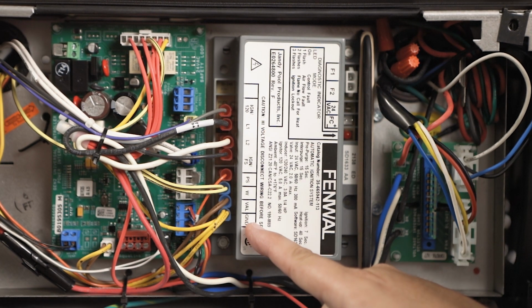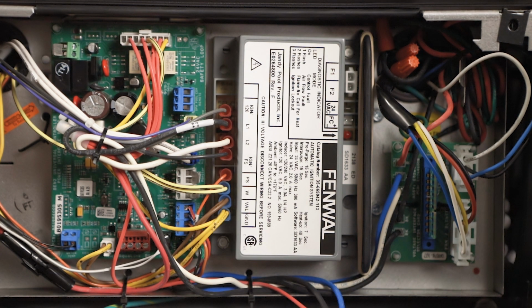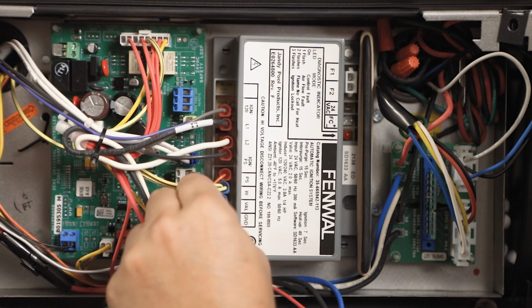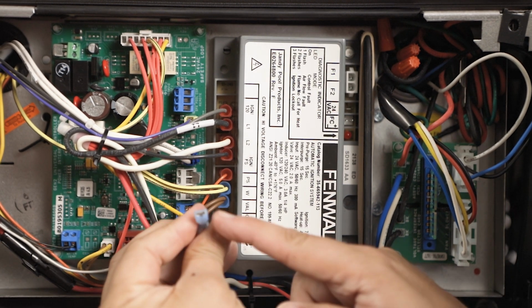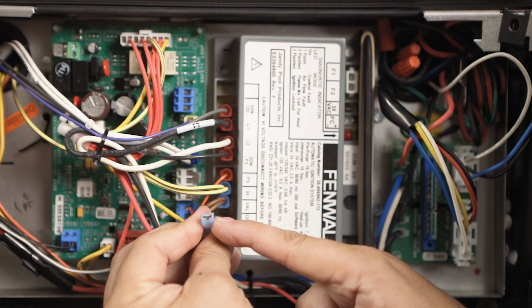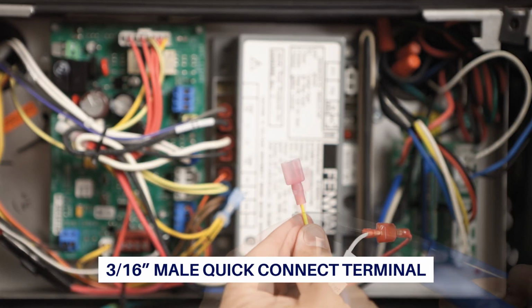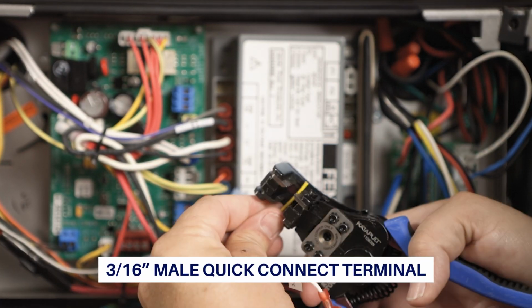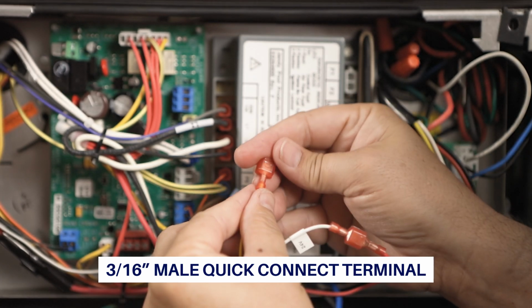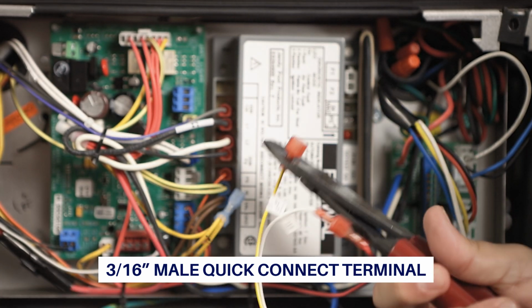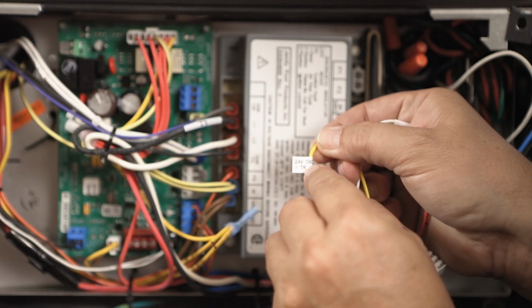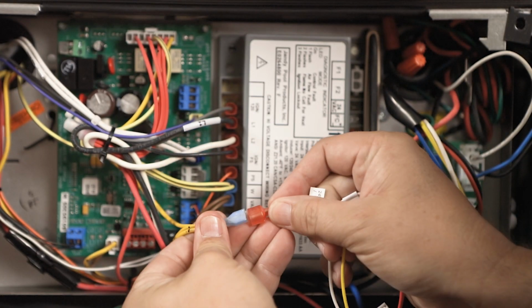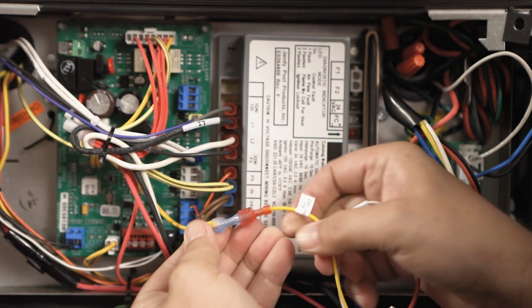The GND terminal has 3 wires connected to it. The 50E47U-843 control has the 24V COM, GND, and MV COM connected internally. Remove the wire from the GND terminal. Note if it is a 1/4-inch or 3/16 spade connector. The 11-pin harness MV GND Quick Connect 1/4-inch male spade must be replaced with a 3/16 male spade to accommodate the existing 3/16 connector spade. Connect the GND wire to the 11-pin harness wire labeled MV GND.